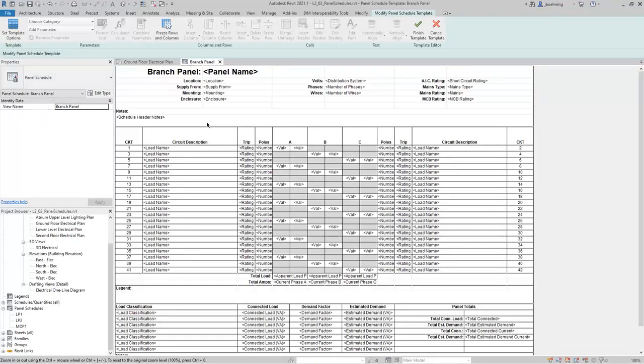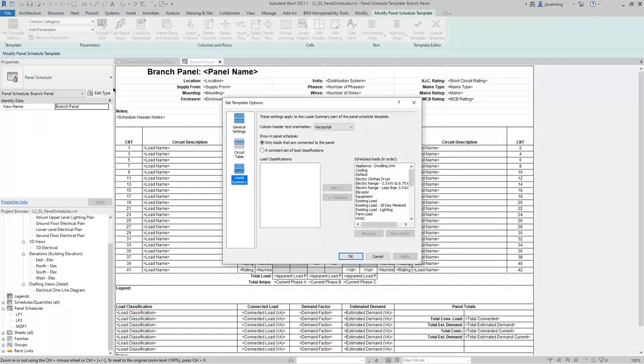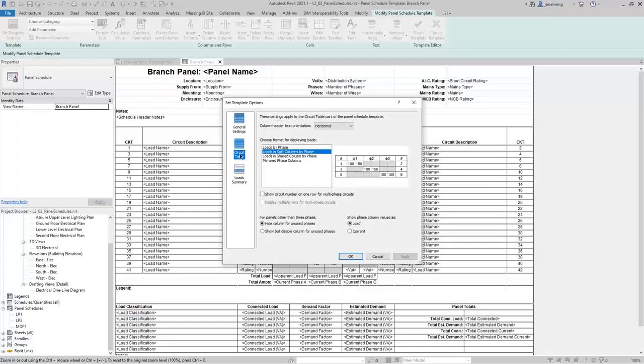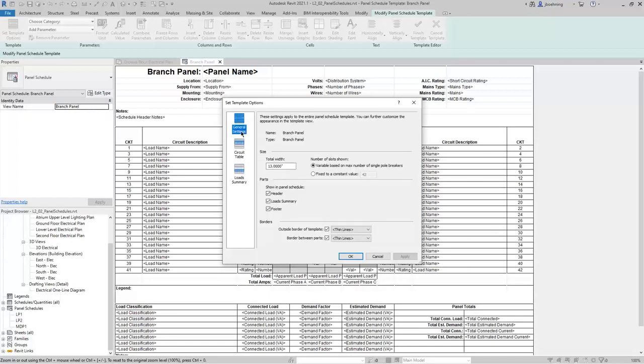There are several controls on the Contextual Ribbon to help you edit and customize your panel schedule template. To begin, click Set Template Options. In this dialog, there are three sets of options: General Settings, Circuit Table, and Loads Summary. In the General Settings, you can control the total width of the panel schedule. You can also control the number of slots shown, which can be set to Variable based on max number of single pole breakers, or fixed to a constant value. Under Parts, you can choose whether or not to show a header, the Load Summary area, or a footer.